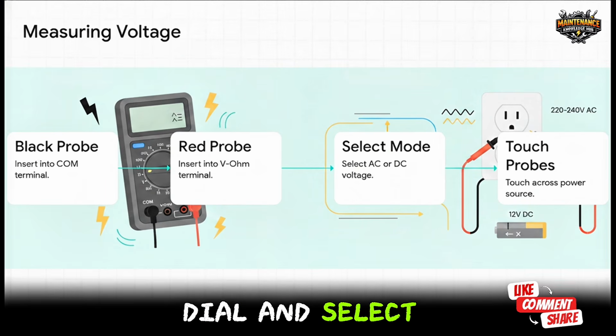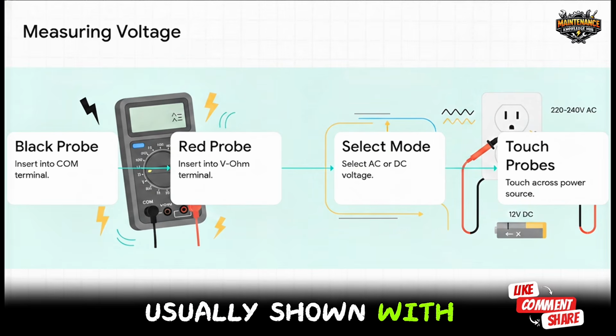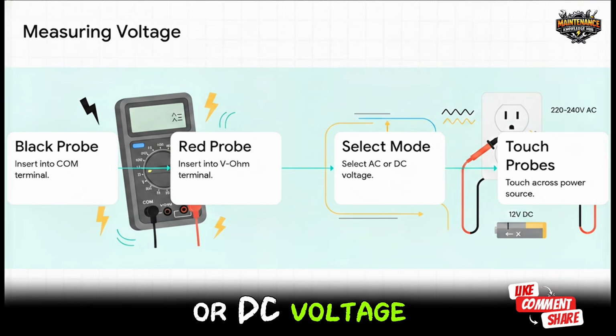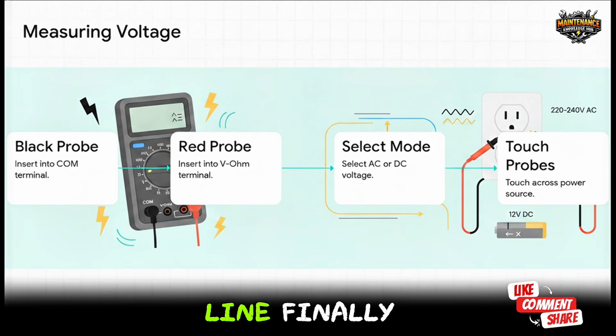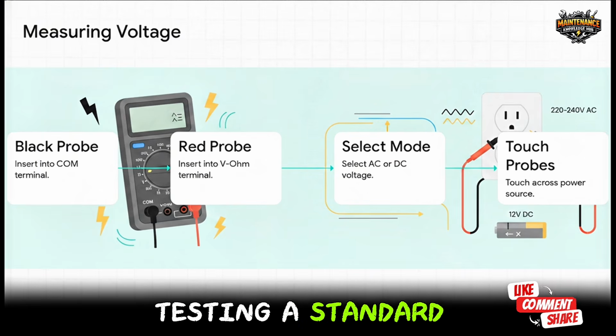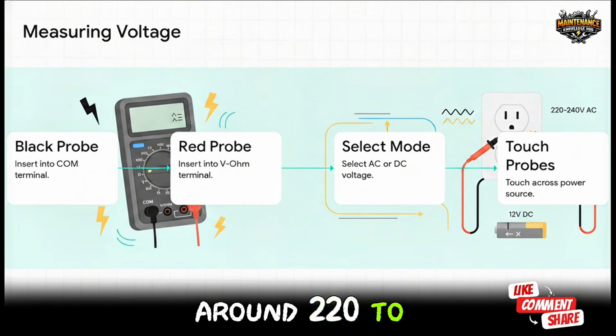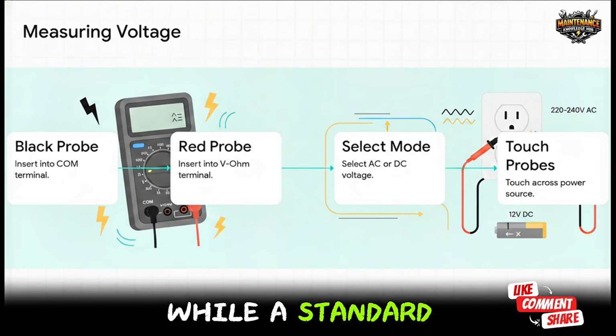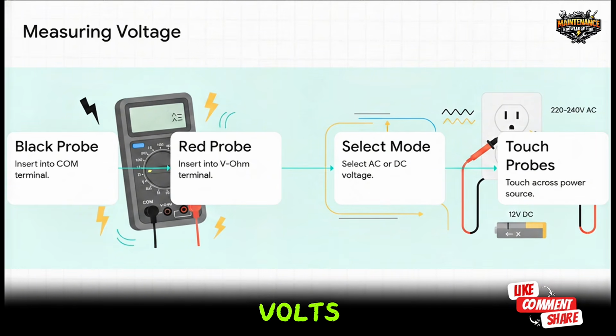Then, grab the dial and select either AC voltage, usually shown with a little squiggly line, or DC voltage, which has a solid and dashed line. Finally, just touch the probes across your power source or component and read the display. To put that into perspective, testing a standard wall outlet will give you around 220 to 240 volts AC, while a standard car battery will read about 12 volts DC.